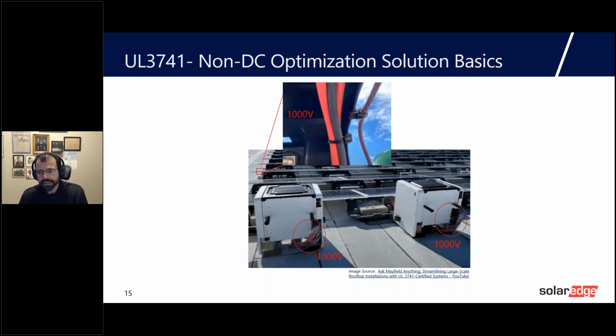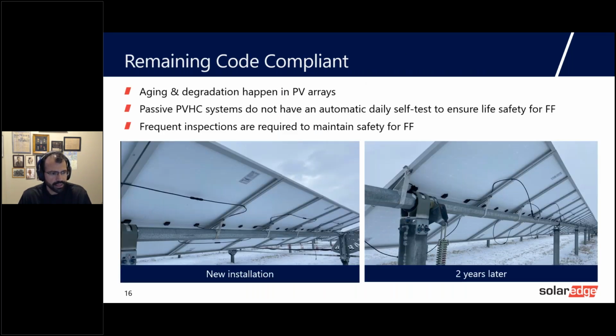As you can see here, some solutions use cable ties. As everybody knows, cable ties will break after a few years. This is something I've seen in the field. I went to an application with a new installation, everything connected together, and after 2 years the cable ties started to fall off. That's the biggest concern. In non-DC optimized systems without integrated rapid shutdown, accessible live wires with voltage levels up to 1,000 volts are held in place by nothing more than plastic cable ties or plastic raceways.